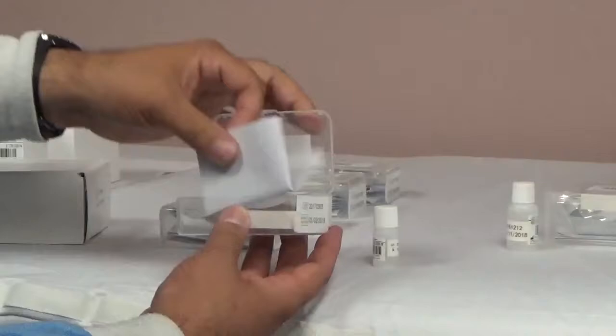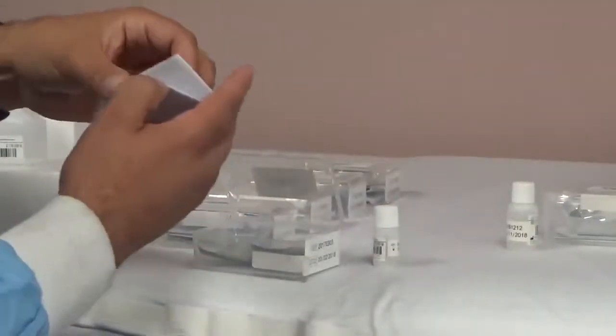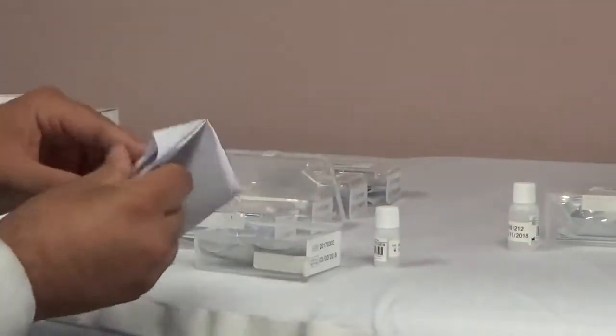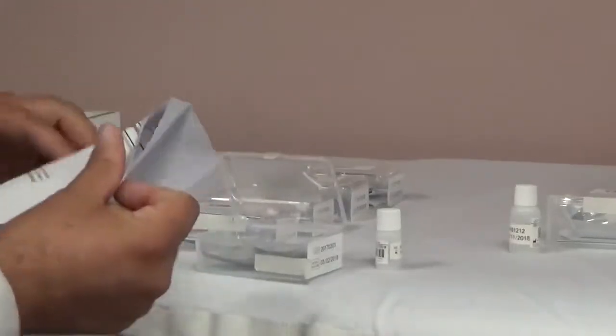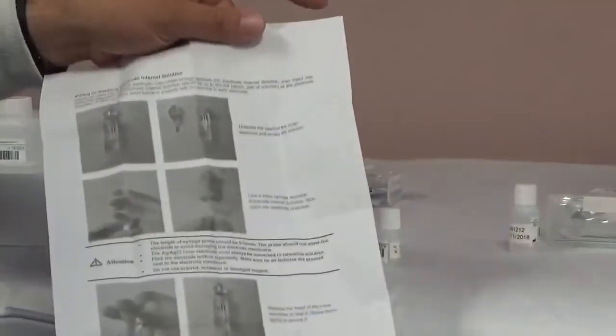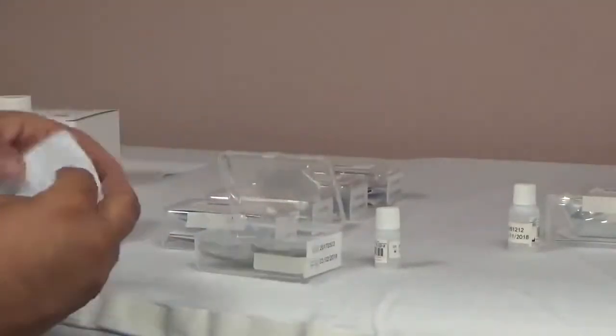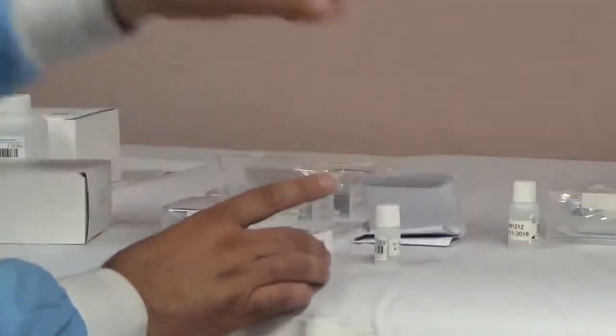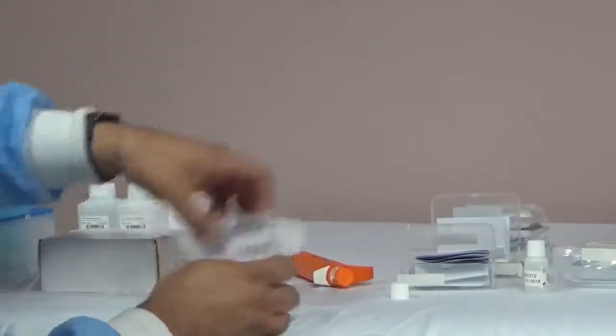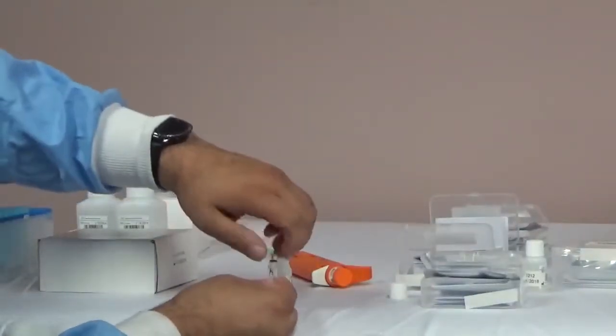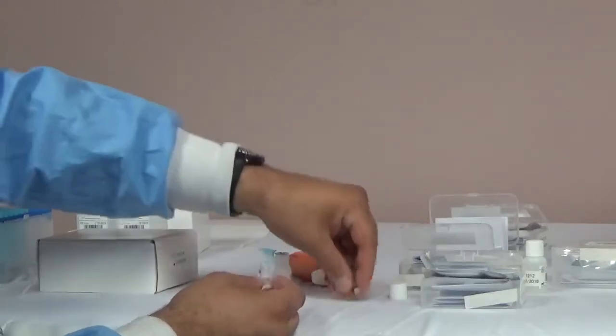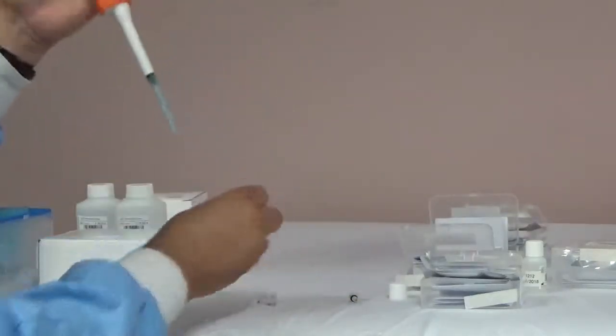Once you have verified that you have all the necessary accessories and consumables, you can begin to fill and install the electrodes. Each electrode package will come with installation instructions. Remove the ISE electrode from the pouch. Unscrew the cap of the electrode by hand, open the ISE refill solution, and pipette 200 microliters of solution into the electrode. When inserting the pipette into the electrode, avoid touching the pipette tip to the bottom, as it could damage the electrode.